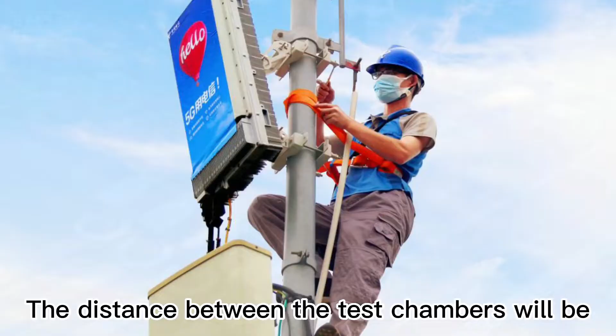This is a trend that will become more evident as it hits 6 GHz frequencies. The distance between the test chambers will be shorter with additional antenna components, favoring OTA. All of this affects testing and makes judgments about what to put in hardware versus software, and what to use analog versus mixed-signal, more difficult. The trade-off is that hardware is quicker and uses less power, but software is more flexible. Analog can be calibrated and modified, but digital is typically set.